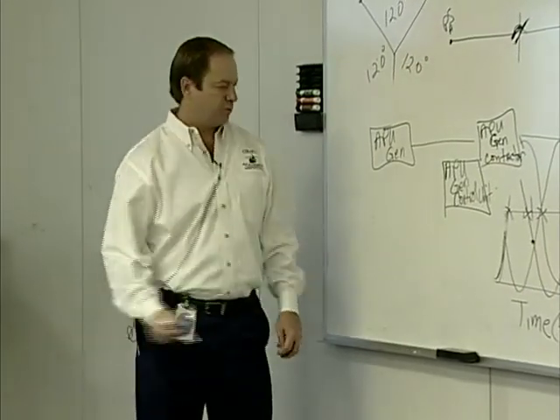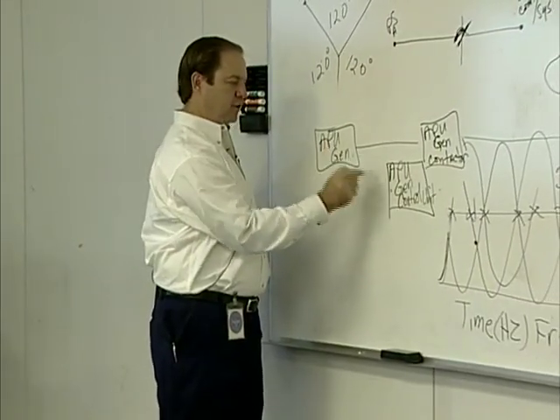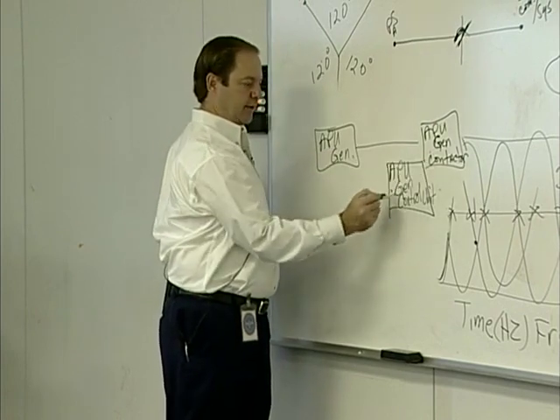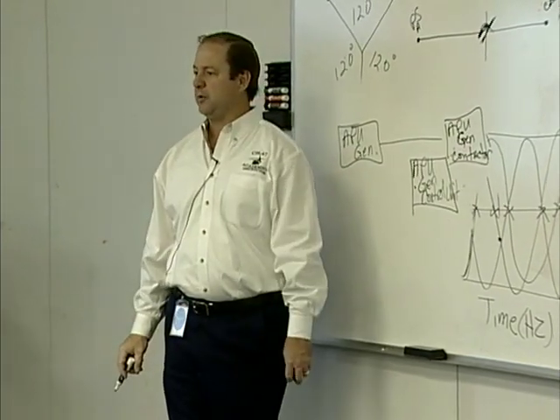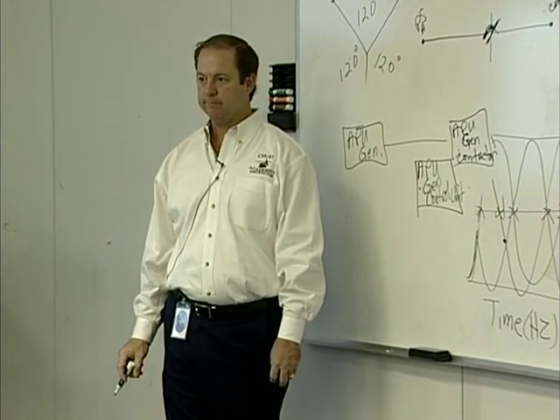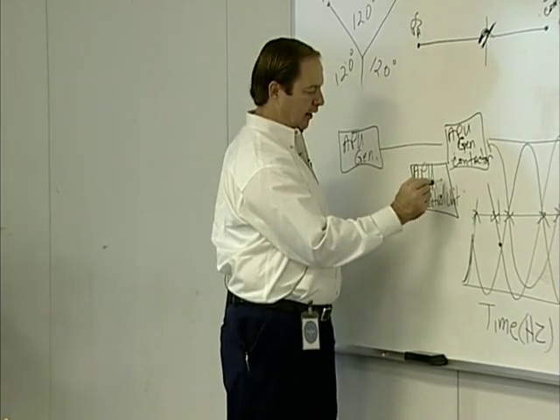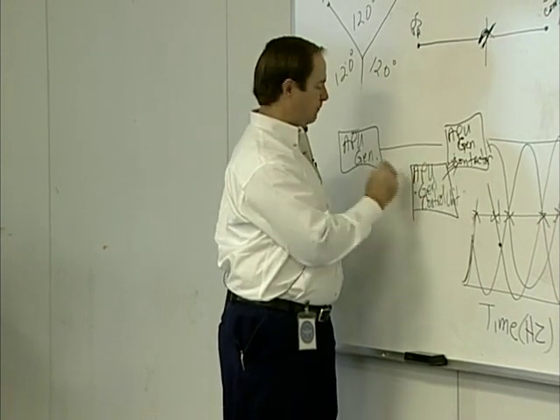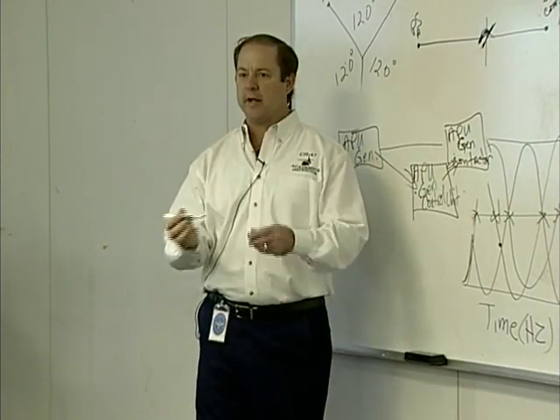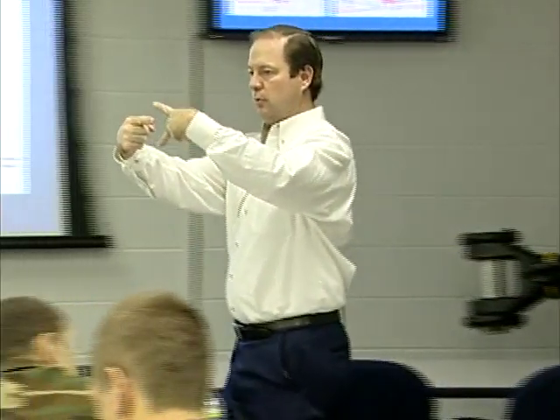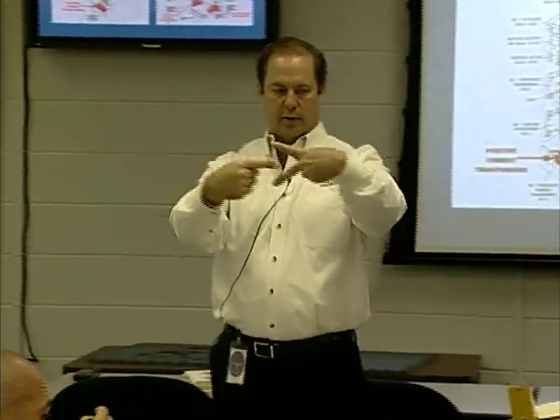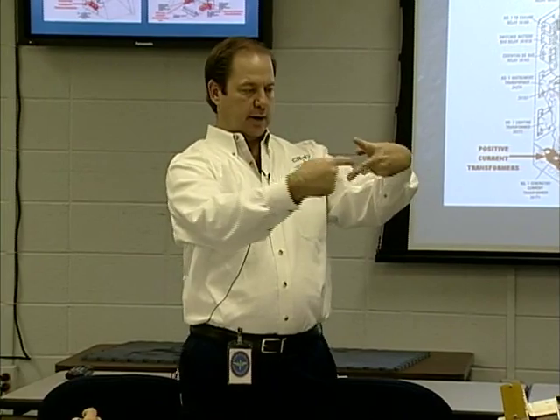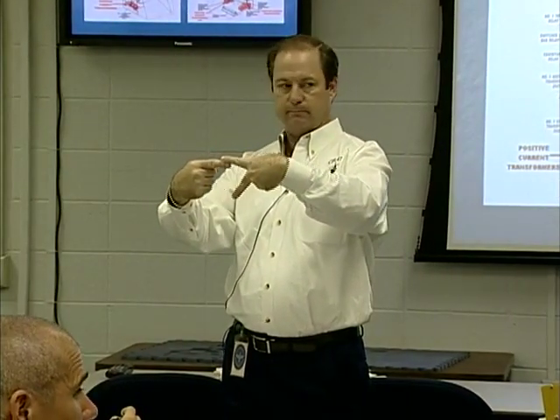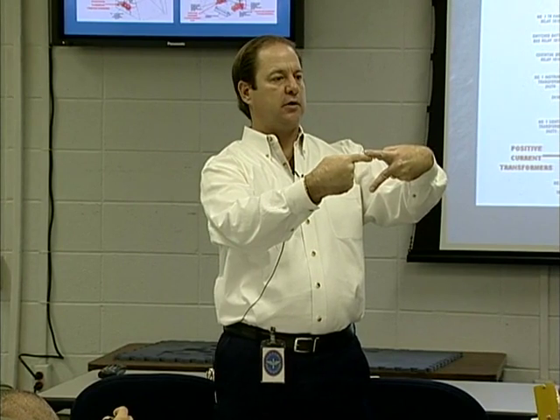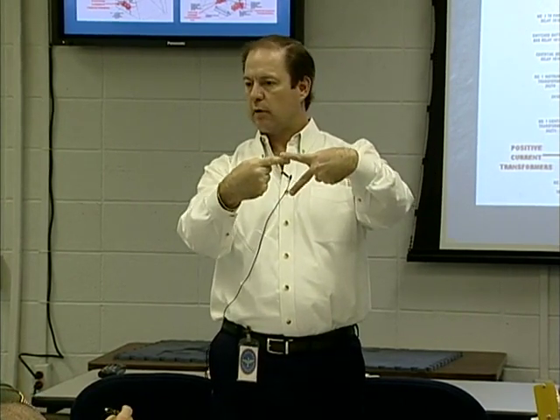Why? Something has to tell this APU generator contactor whether or not power is being provided, agreed? So that APU generator control unit, based on receiving power and saying 'yep, my APU generator is powered up,' is now going to cause that contactor to do this. Here's what's going on inside that contactor: it's just going to go like this, and now it's going to allow its power to continue on its merry way. Everyone tracking that?